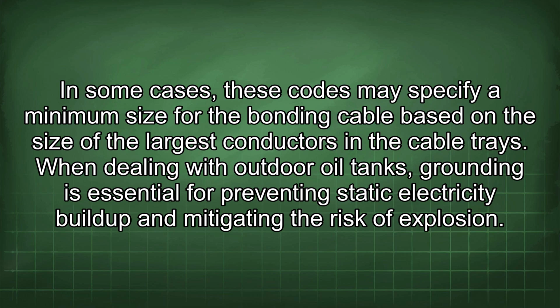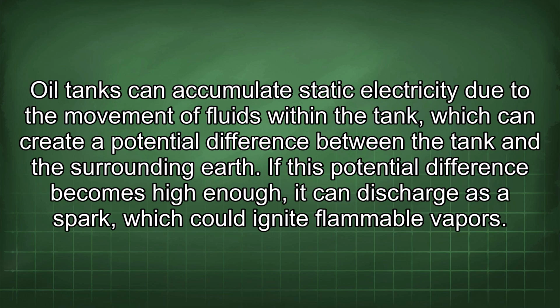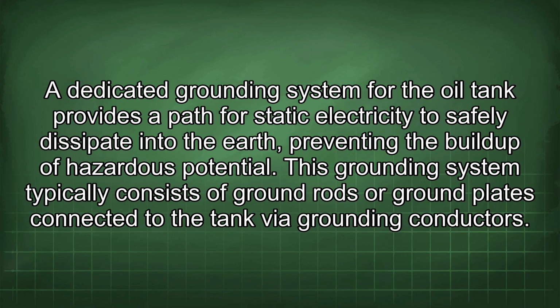When dealing with outdoor oil tanks, grounding is essential for preventing static electricity buildup and mitigating the risk of explosion. Oil tanks can accumulate static electricity due to the movement of fluids within the tank, which can create a potential difference between the tank and the surrounding earth. If this potential difference becomes high enough, it can discharge as a spark, which could ignite flammable vapors. A dedicated grounding system for the oil tank provides a path for static electricity to safely dissipate into the earth, preventing the buildup of hazardous potential.